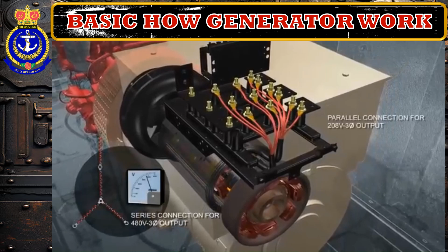To simplify wire connections, Doosan mobile generators have a convenient selector switch. When an operator selects the desired voltage, the switch adjusts the connections, and current flows through a protective device called a circuit breaker. If current exceeds capacity, the breaker halts the system, protecting the generator and connected equipment from potential damage.